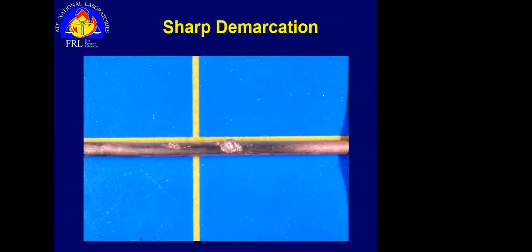Okay, again, I'm not a huge fan of using a single conductor, but sometimes that might be all you have, because maybe you pull a conductor out of conduit and the other side of the arc site is the conduit itself. And nobody has the time, nor usually the equipment, to section conduit from end to end to find the arc site on the inside. But I know this was arc melting created by arcing because it was a lab generated test burn. So I know for a fact it's what it is, but you can see very pristine conductor up until the area of the damage, and then it's pristine beyond that. You can see some longitudinal lines here, and I'll get to those in a little bit. It's a later characteristic, but it's something to keep in the back of your mind.